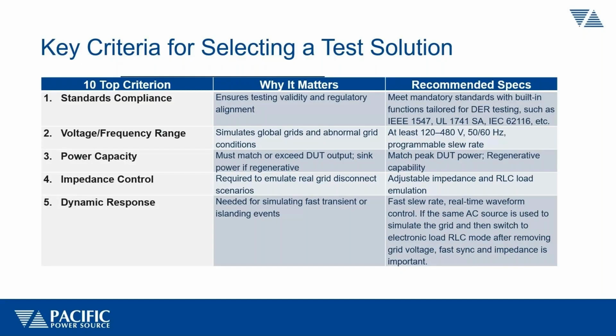You have to support enough power to run the test setup, so you need sufficient voltage, current, and power ratings on your grid simulator, and you need to be able to disconnect the grid power. If you're using an electronic load, you have to be able to control the load impedance RLC components accurately. Some of these tests are relatively fast. You're looking at disconnect times that are less than a few seconds, so you have to be able to capture that event accurately enough to measure the time accurately. That's generally done by some of the test equipment you have, and typically an oscilloscope is one of the best and most common ways to do that.